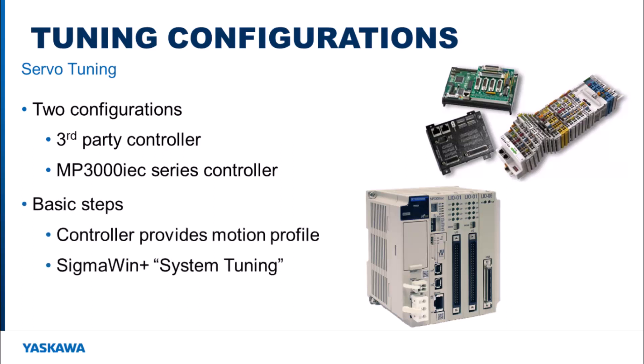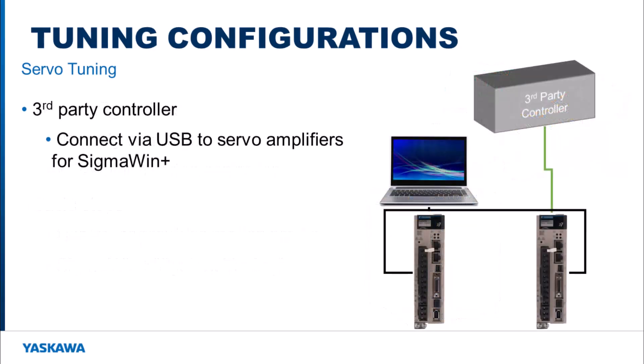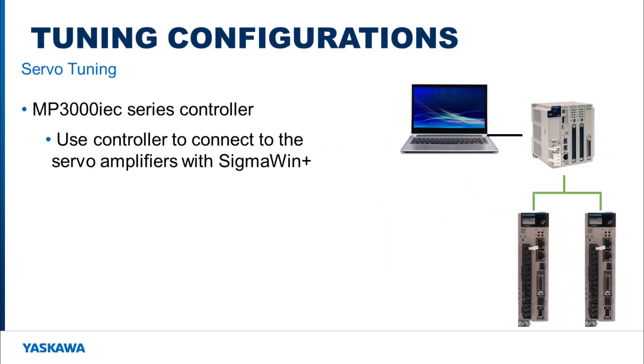Since both motors can be accessed at the same time, SigmaWin+ system tuning can be used to tune them. If a third-party controller is being used, the computer running SigmaWin+ needs to be connected to each servo amplifier via a USB cable. Using an MP3000 IEC series controller allows you to connect to multiple servo amplifiers using SigmaWin+ over Mechatrolink instead of connecting to each one with a USB cable.